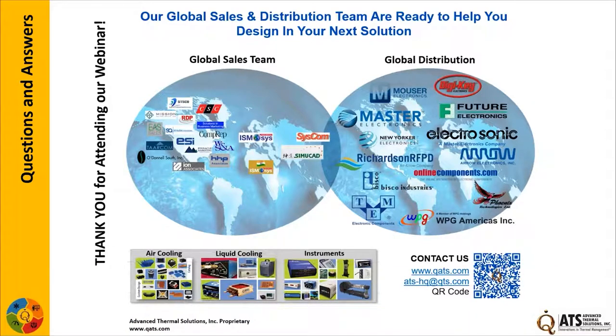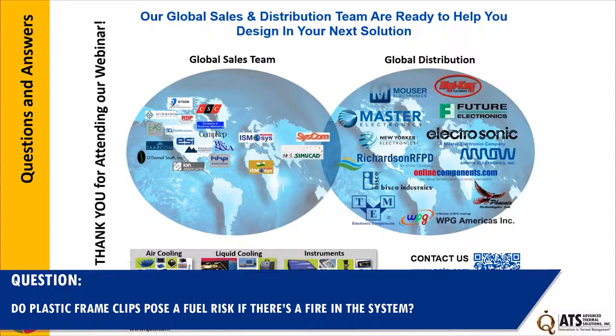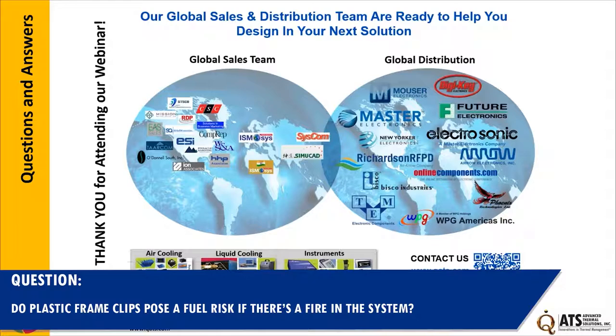Another question: do plastic frame clips pose a fuel risk if there is a fire in the system? No. Our frame clips are made from specific engineering polymers that pass the UL 94V-0 specifications for flame resistance. We actually have a video on YouTube of us holding a blowtorch up to one of our attachments, and the heatsink stays secure even with the plastic frame clip exposed to that flame. We're not adding fuel to the assembly, which is a big requirement in many telecom applications.